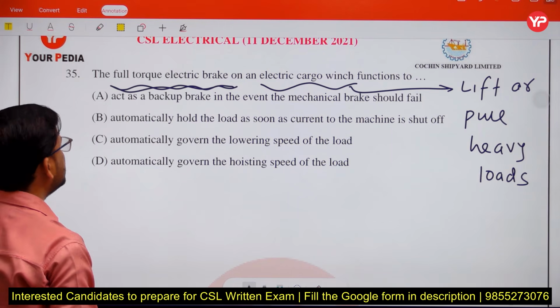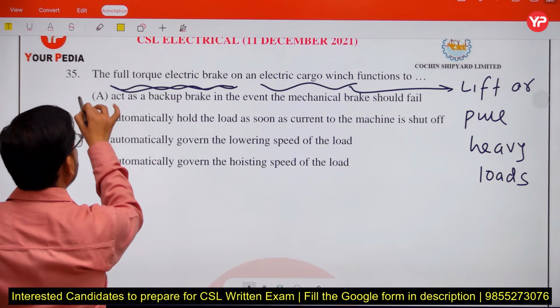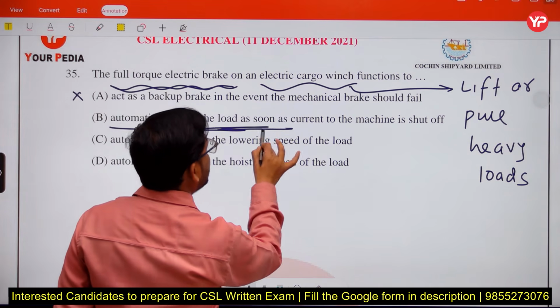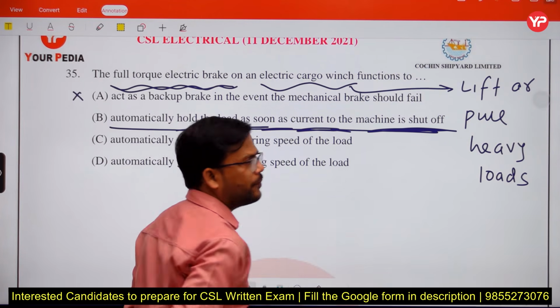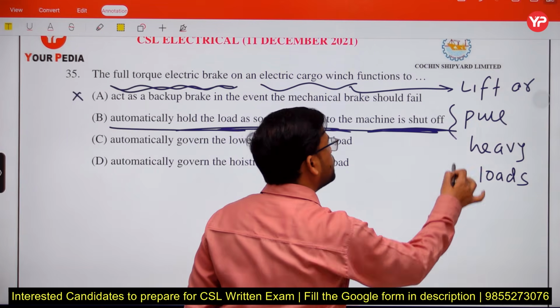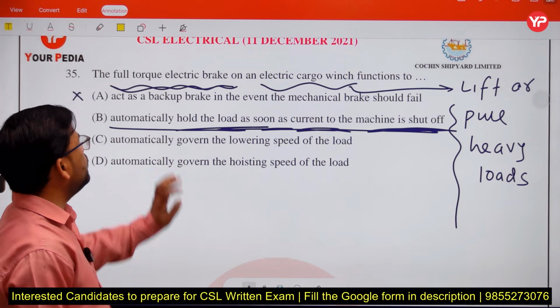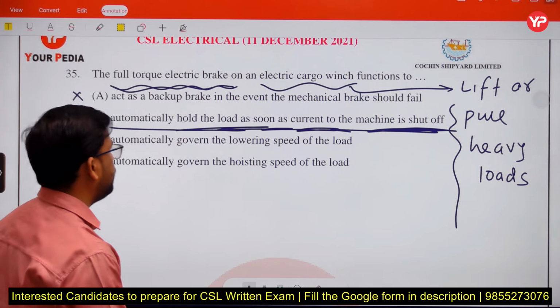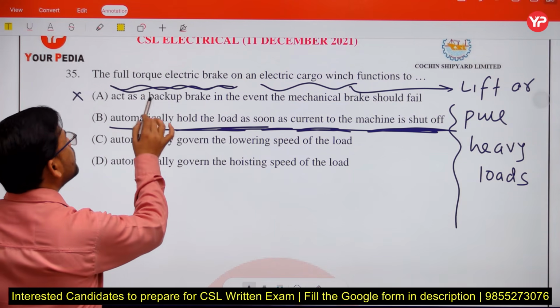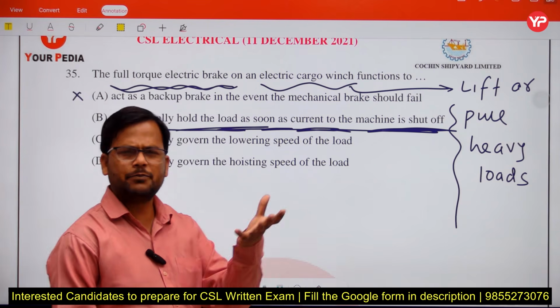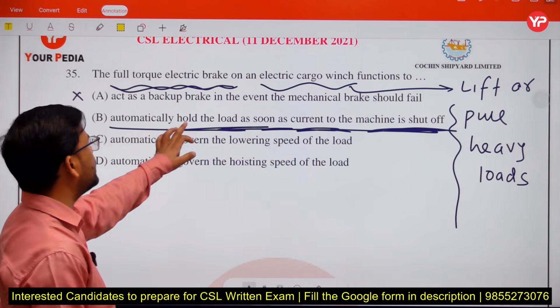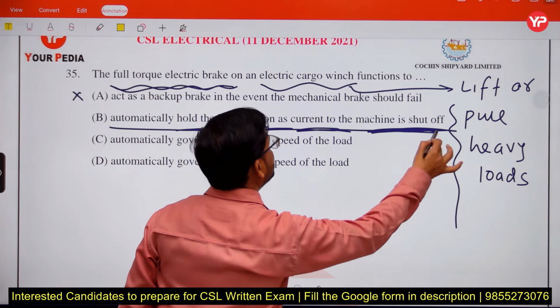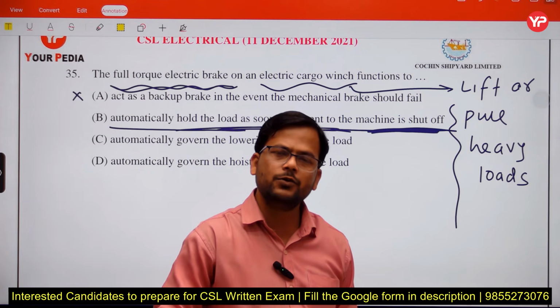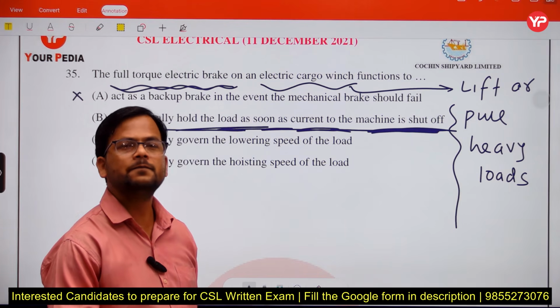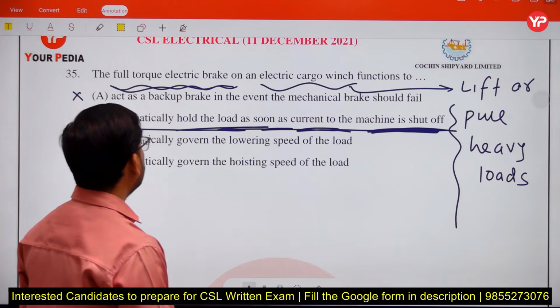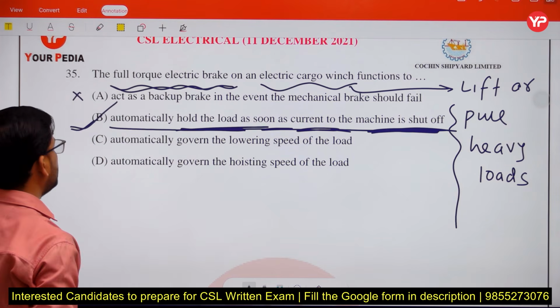So the correct answer is: act as a backup brake - no. Automatically hold the load as soon as current to the machine is shut off - yes. When current to the machine is shut off, the full torque electric brake automatically captures the load at that position. So it automatically holds the load as soon as current is shut off. When machine current equals zero, the full torque electric brake controls the load, taking a grip and holding it. So the correct answer is option B.